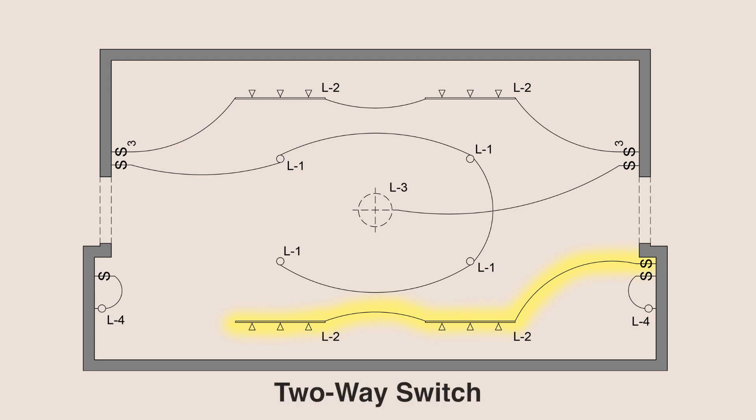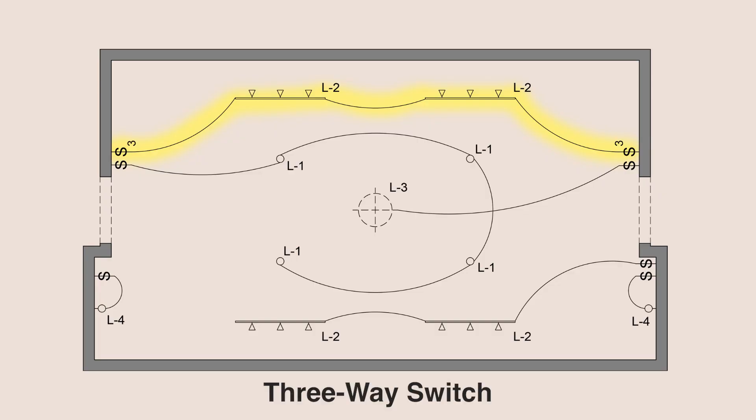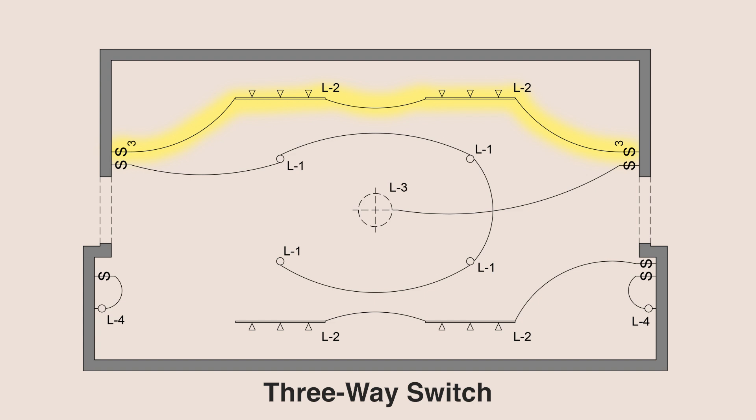These track lights on the same circuit are controlled by one single switch — this is called a two-way switch, or sometimes referred to as a single pole switch. In the case where you have two entrances in a room, say on opposite ends, you can have two light switches, one at each door, which would be a great idea so users can access the lights from both entry points. Some other good locations for two switches are at the top and bottom of a staircase and at either end of a really long hallway. This would be called a three-way switch. These terms can be confusing because they don't refer to the number of switch locations — they instead refer to the number of conductors required to make switching possible.